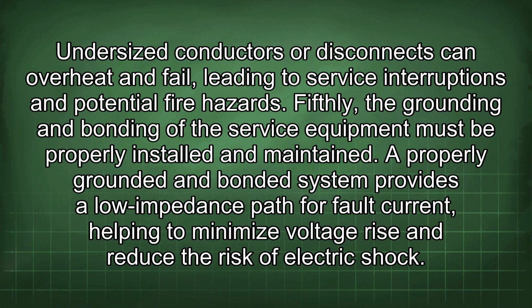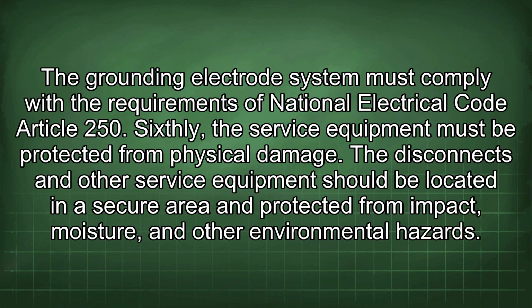Fifthly, the grounding and bonding of the service equipment must be properly installed and maintained. A properly grounded and bonded system provides a lower impedance path for fault current, helping to minimize voltage rise and reduce the risk of electric shock. The grounding electrode system must comply with the requirements of National Electrical Code Article 250.